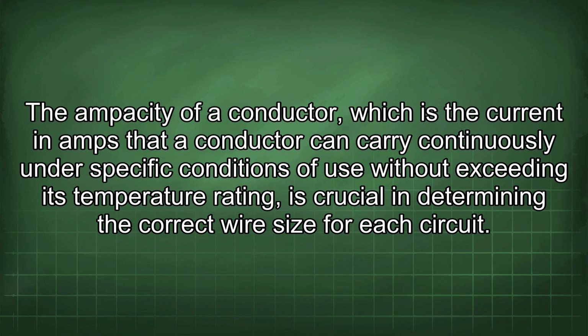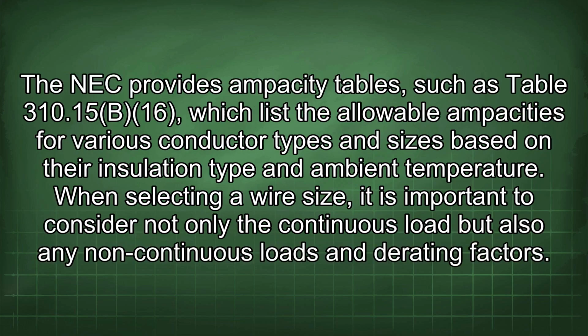The ampacity of a conductor, which is the current in amps that a conductor can carry continuously under specific conditions of use without exceeding its temperature rating, is crucial in determining the correct wire size for each circuit. The NEC provides ampacity tables, such as Table 310.15(B)(16), which lists the allowable ampacities for various conductor types and sizes based on their insulation type and ambient temperature.